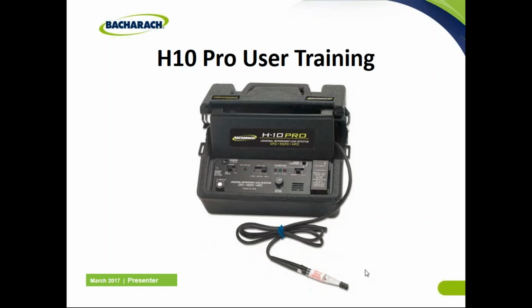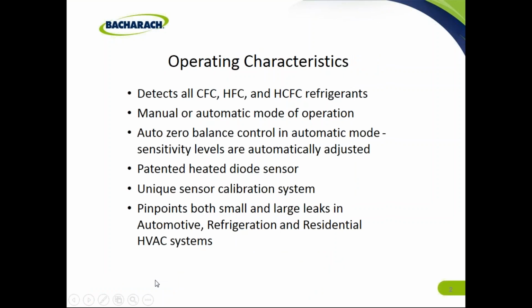This presentation is on the Bacharach H10 Pro leak detector. We will go over the settings, the control setup, and the operation of the unit. The Bacharach H10 Pro detects all CFCs, HFCs, and HCFC refrigerants. It has both a manual and automatic mode of operation. The auto zero balance control and the automatic mode sensitivity levels are automatically adjusted. It has a patented heated diode sensor, a unique sensor calibration system, and it pinpoints both small and large leaks in automotive, refrigeration, and residential systems.